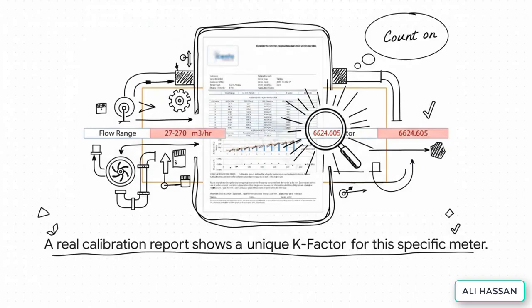And this isn't just some abstract idea. Check this out. This is a real factory calibration report. And you can see that this specific meter has a K-factor of 6,624.605. It's that incredible precision that lets an engineer completely trust the numbers they're getting from it.